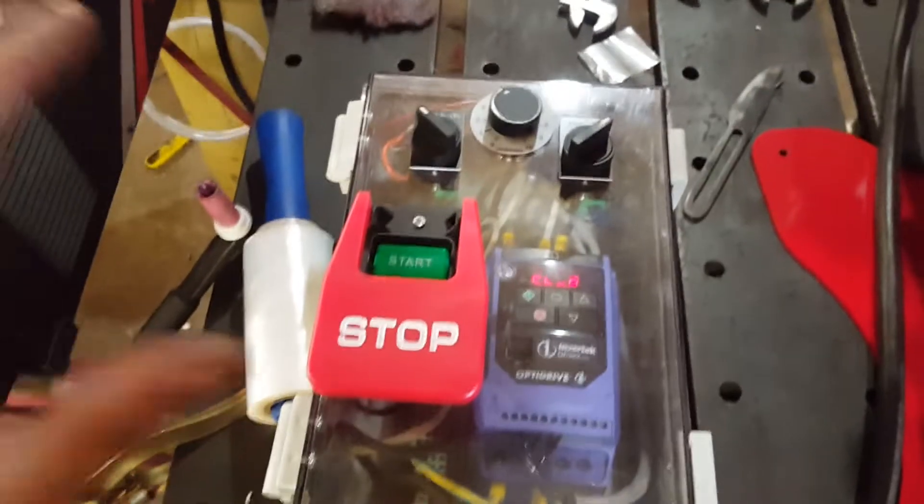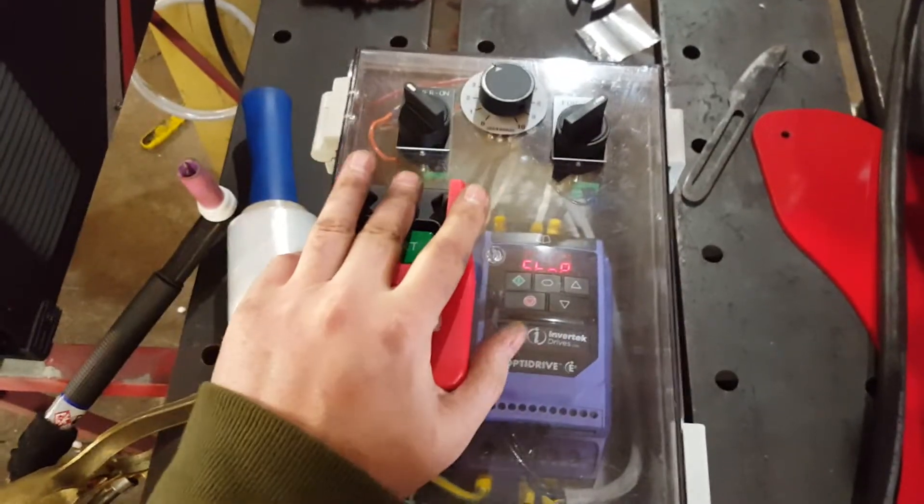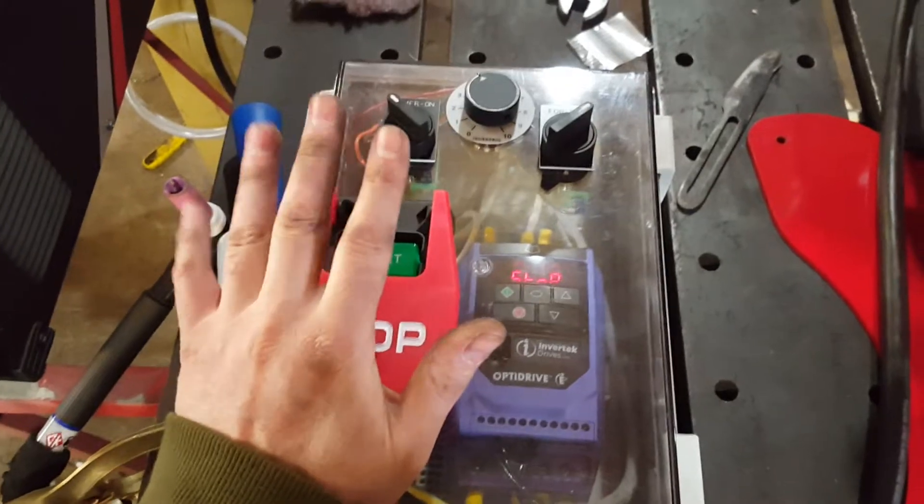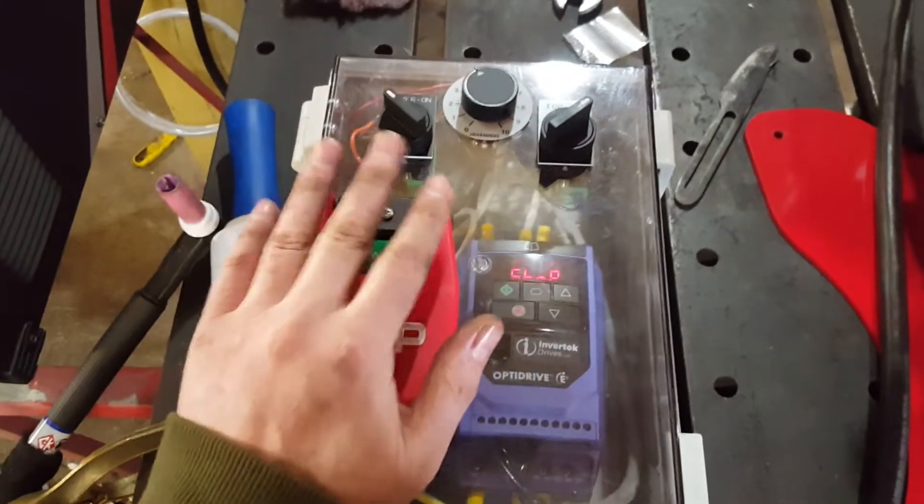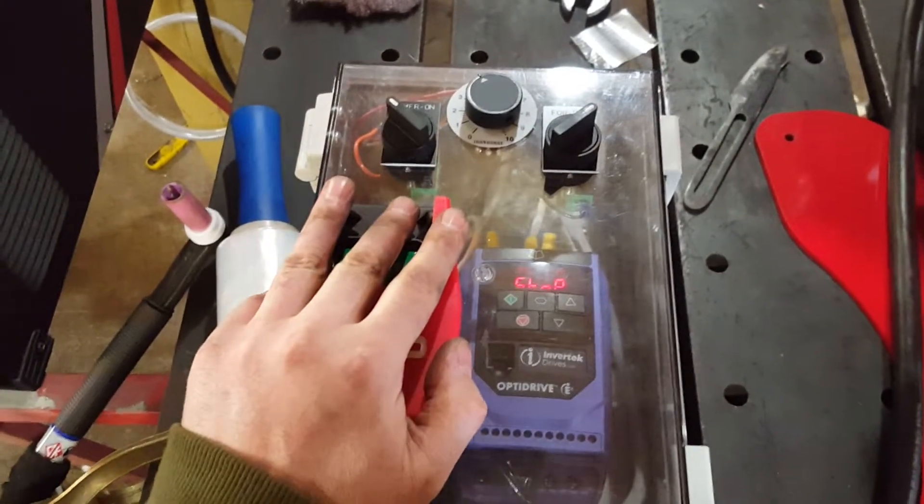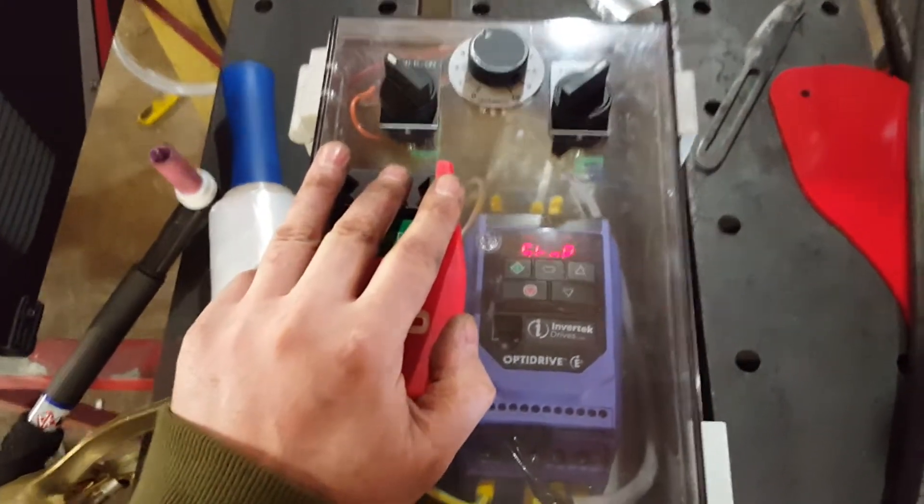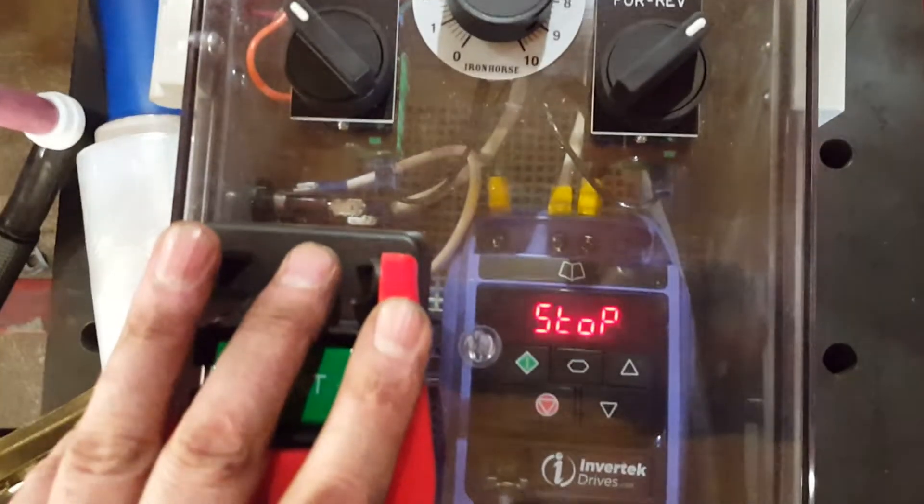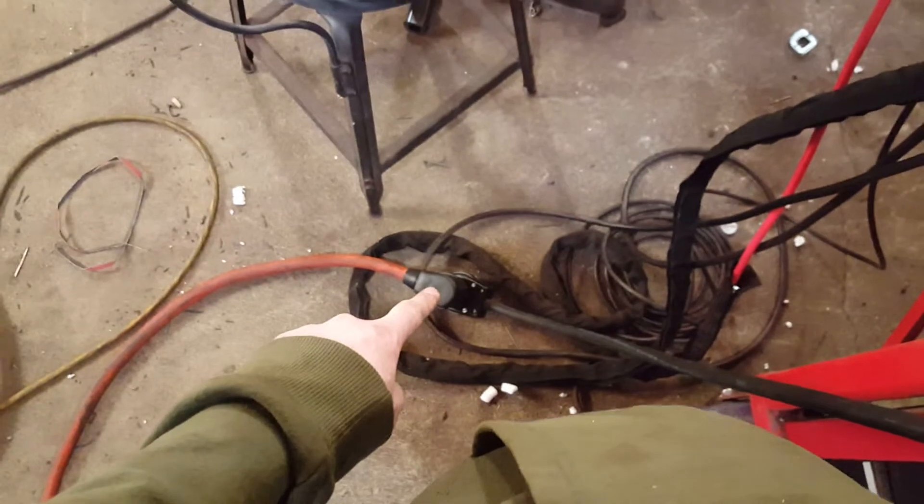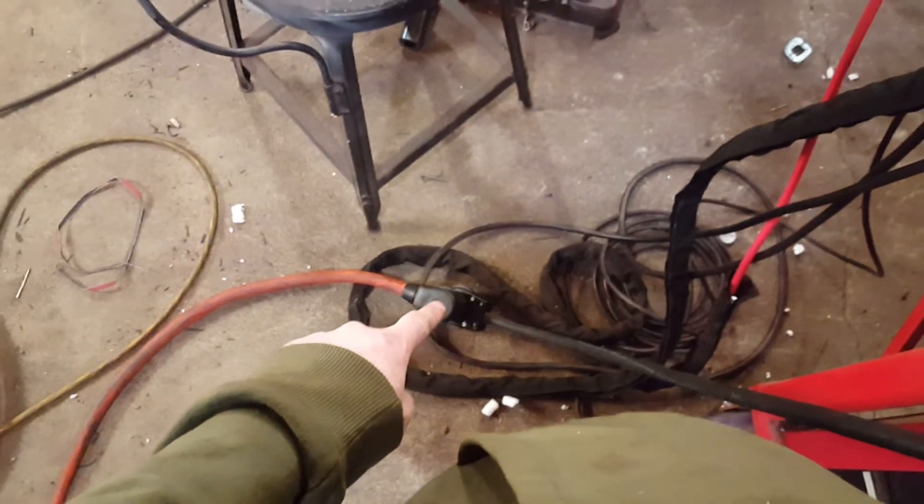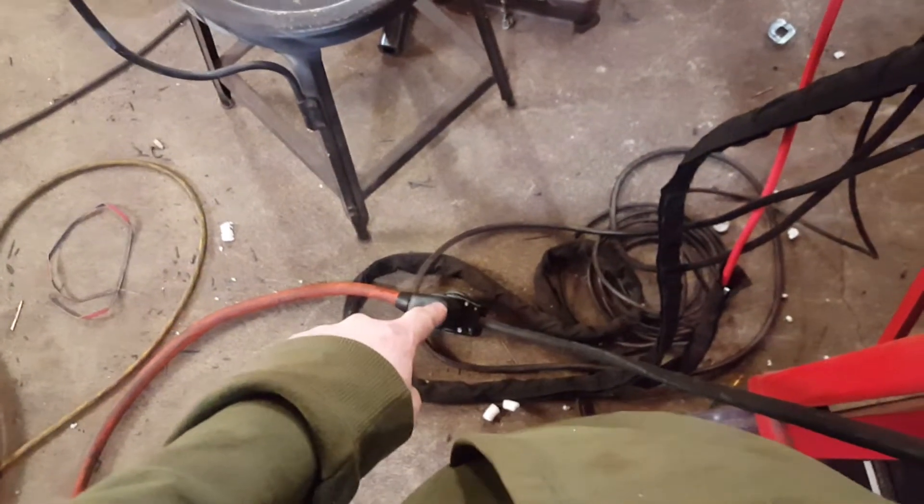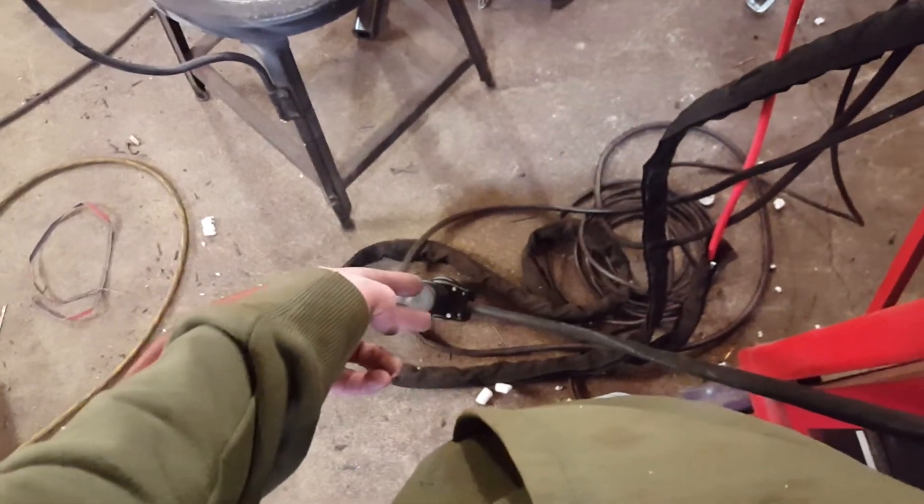You do need a power disconnect. Well, you don't have to, but if you don't have a power disconnect and you unplug this drive, as long as those lights are on, the plug on the other end is still hot. So the capacitors will discharge if you touch that to a metal table or your body.